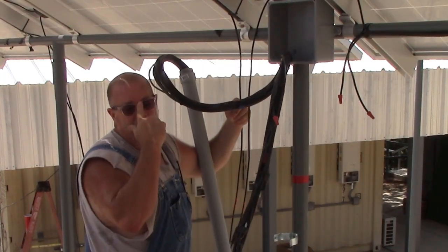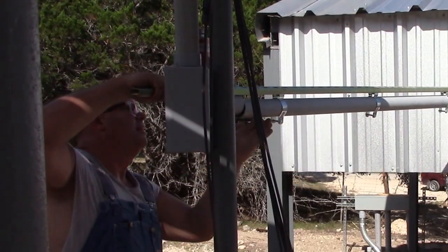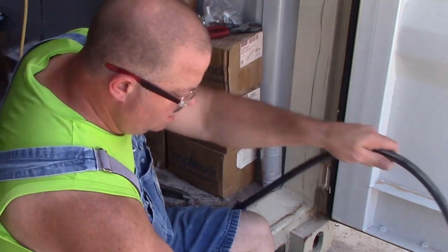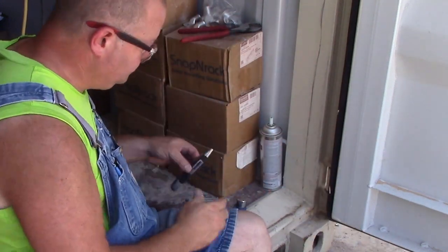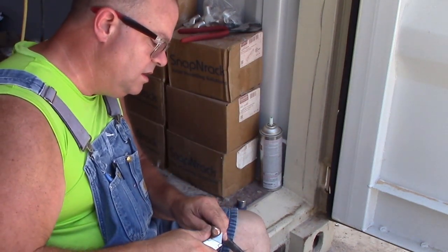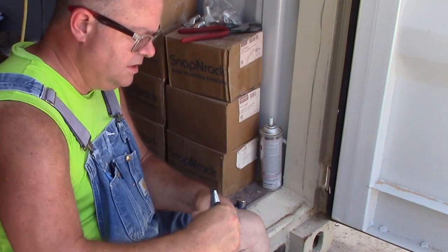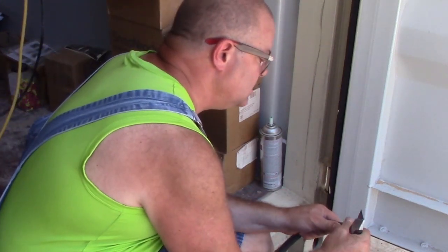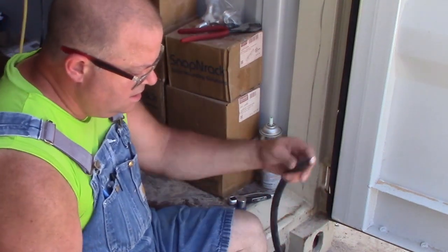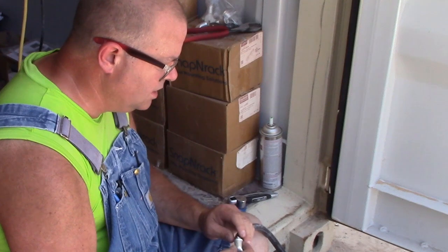It's 32 kilowatts of solid power here. Those fans you hear — those are the battery fans every 30 seconds. I've got them adjusted on high because they're charging fast right now. They run for 30 seconds, evacuate all the gas out of the battery cabinets, and then wait for 30 seconds before starting again. As the system charges up, it can make a lot of poison gas.